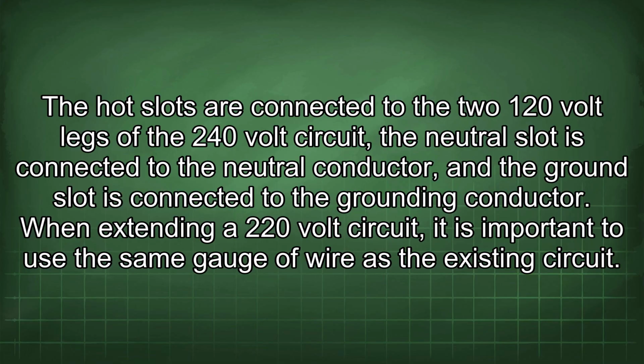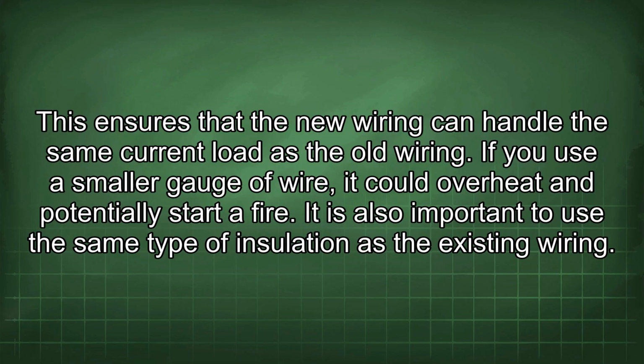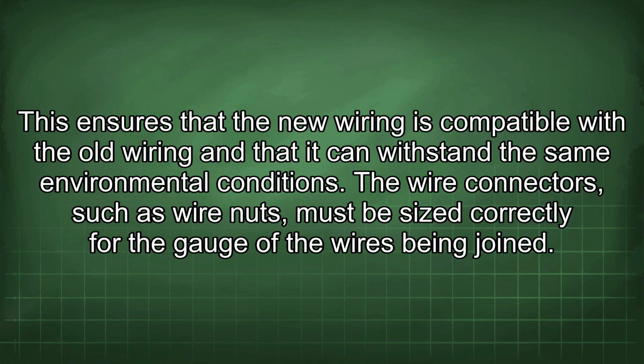When extending a 220-volt circuit, it is important to use the same gauge of wire as the existing circuit. This ensures that the new wiring can handle the same current load as the old wiring. If you use a smaller gauge of wire, it could overheat and potentially start a fire. It is also important to use the same type of insulation as the existing wiring. This ensures that the new wiring is compatible with the old wiring and that it can withstand the same environmental conditions.